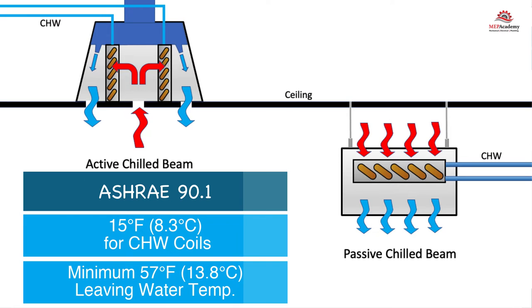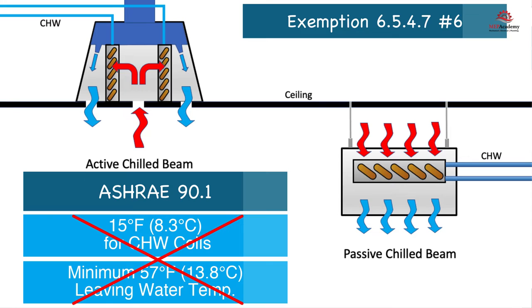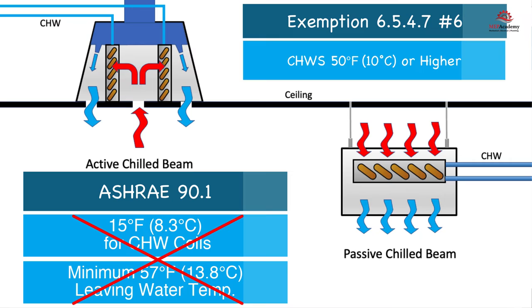The smaller delta T requires greater flow compared to a typical VAV chilled water coil under ASHRAE 90.1, which requires a 15 degree Fahrenheit (8.3 degrees Celsius) temperature difference between supply and return, with a minimum leaving water temperature of 57 degrees Fahrenheit (13.8 degrees Celsius). Chilled beams are excluded from these mandatory delta T requirements of ASHRAE 90.1; exception 6.5.4.7 number 6 states that coils with design entering chilled water temperatures of 50 degrees Fahrenheit (10 degrees Celsius) and higher are exempt.